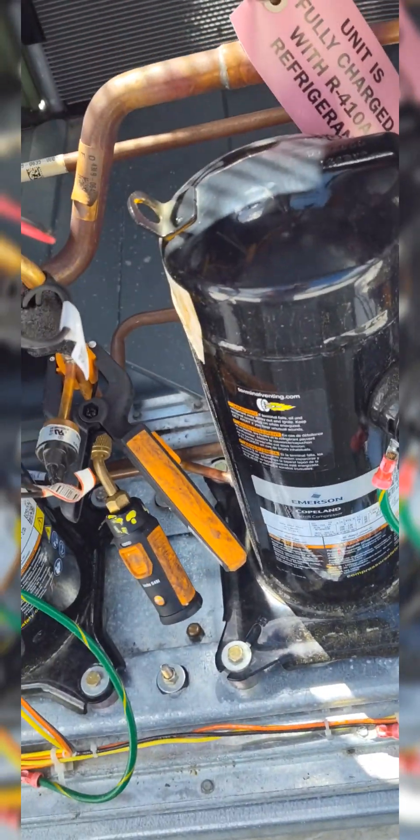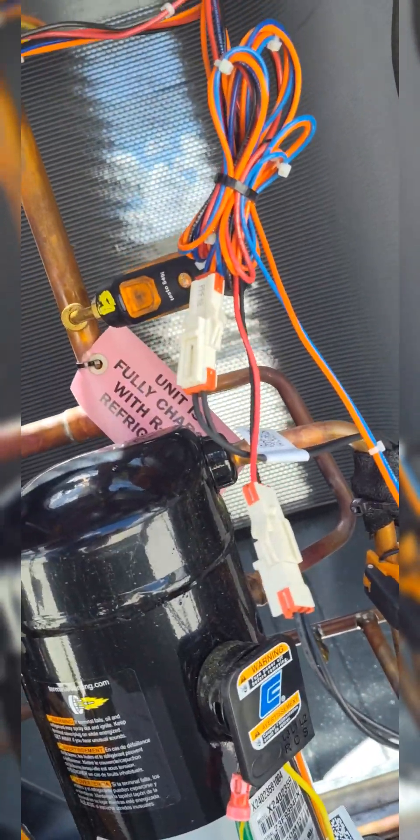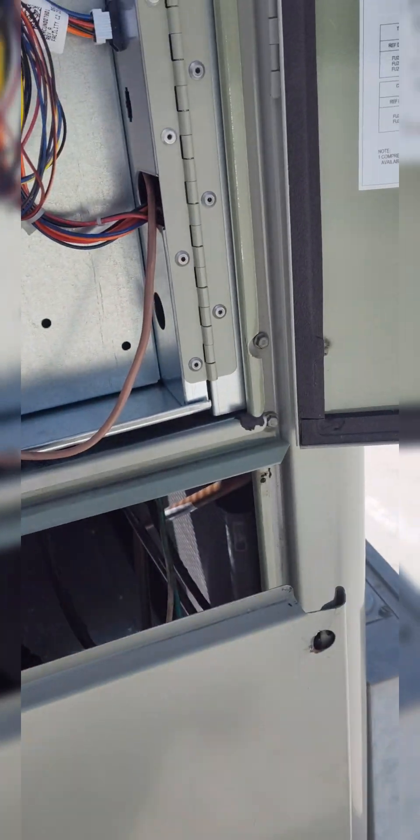Go back to my Testos. I got temperature clamps on both my discharge lines. You have a discharge sensor, high pressure, low pressure - all of them could cut it out. So it is what it is.